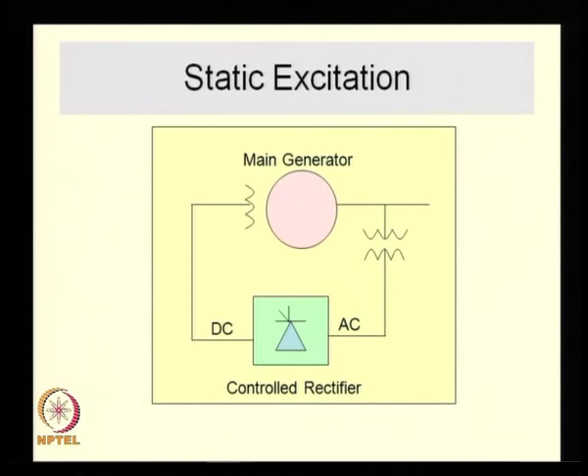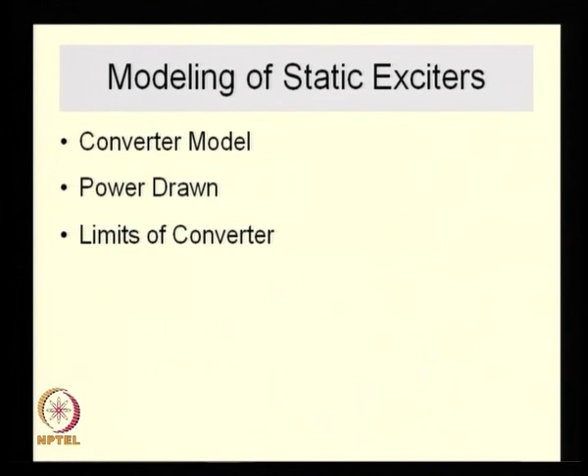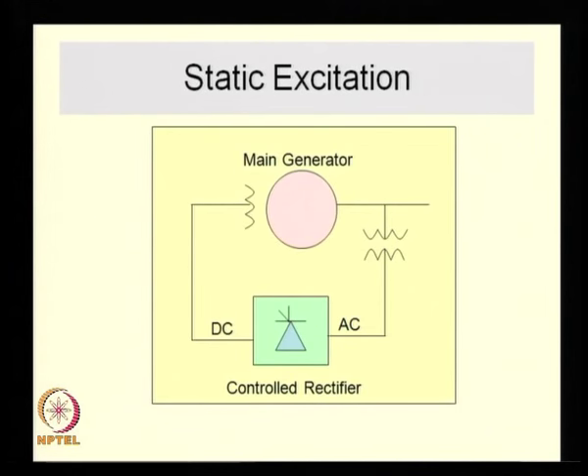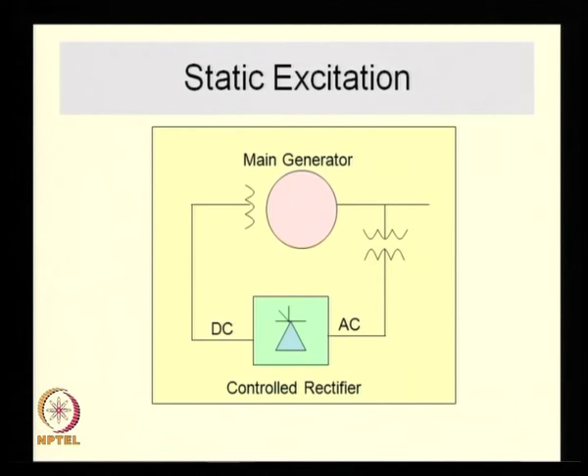To model this static excitation system for stability studies, we need to represent its various components. One important point is that a static excitation system draws a bit of power and slightly loads the main generator. However, the amount of excitation power required is very small compared to the overall rating of the synchronous machine, so we need not even consider the loading effect of the excitation system on the main generator.